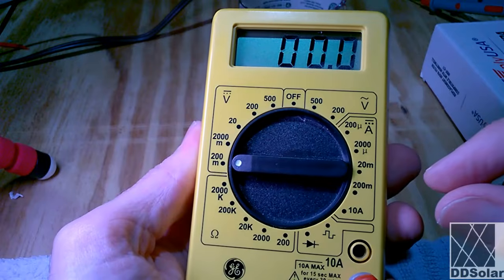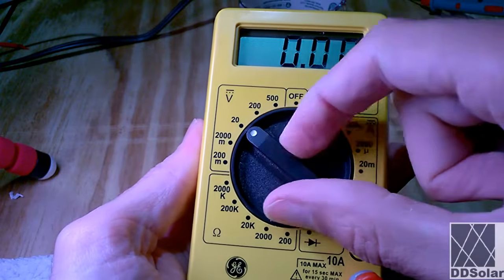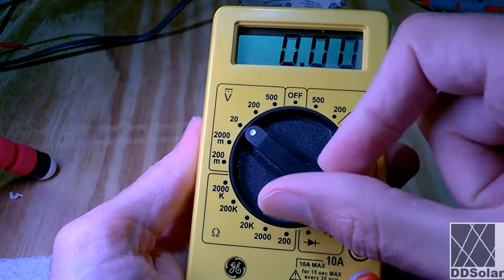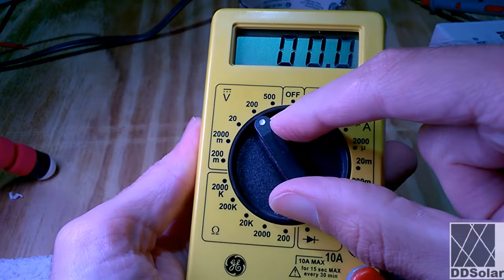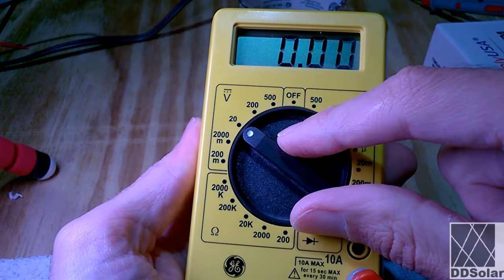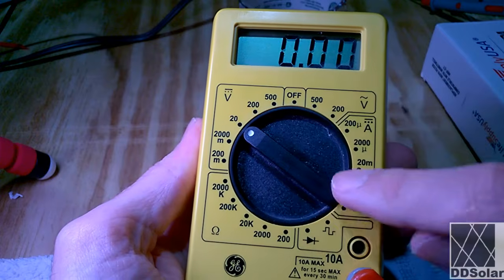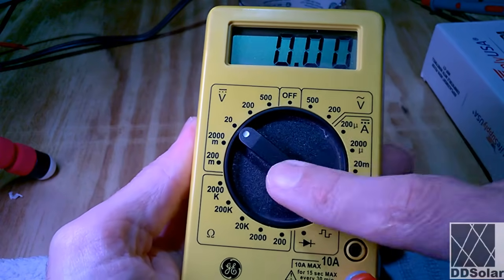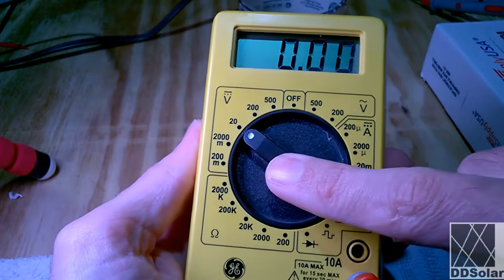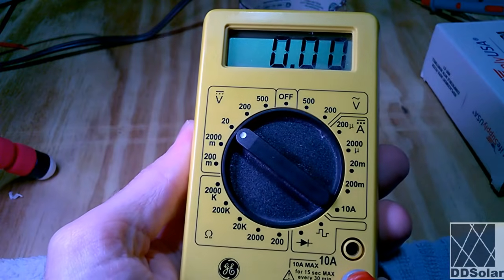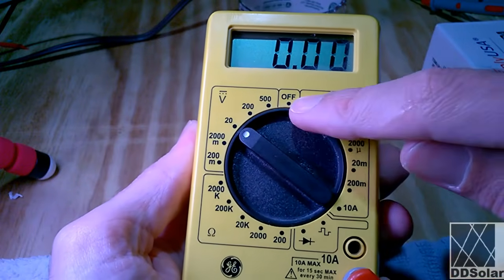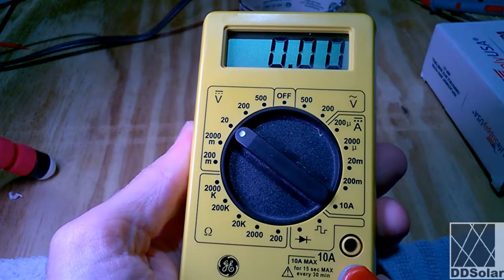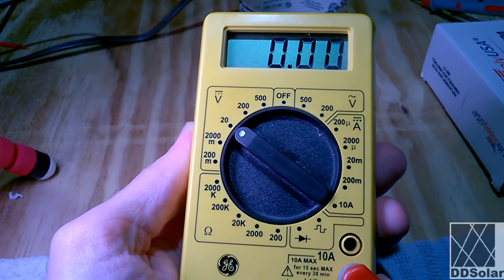So if you're ever getting strange readings, one of the things you can do is put it back on the setting, switch it over, and watch the dial. What should happen is the meter should zero out. You can also try pushing on the dial. Sometimes if you push on the dial, you'll see the meter change its behavior, and that's usually a red flag. It could mean that the switch in here needs to be opened up and cleaned out with electronics contact cleaner, or perhaps it is faulty.